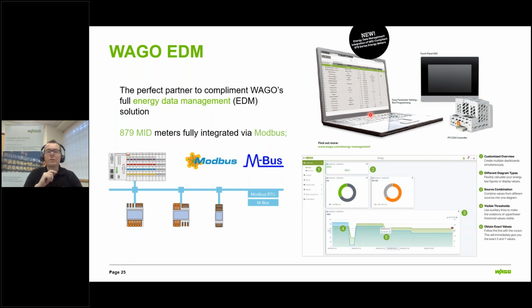Essentially it's sold by a license per controller. These controllers are a standard, what might be referred to as a PLC, a programmable logic controller, which when initially supplied out of the box have actually no function. They have to have a project, a program written that makes them do what they're intended for. They're very versatile, and one of the things they can do is act as an energy management system. So the software is already written. You essentially purchase a license, and we can come back to you with pricing on that as well as the hardware costs.